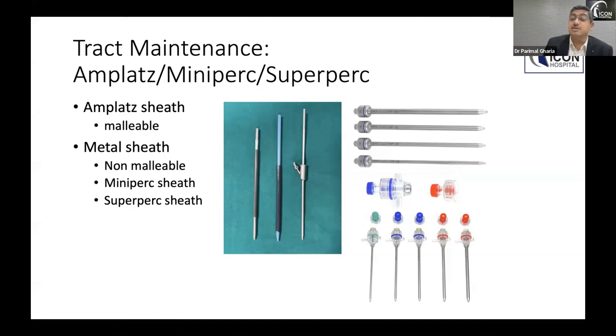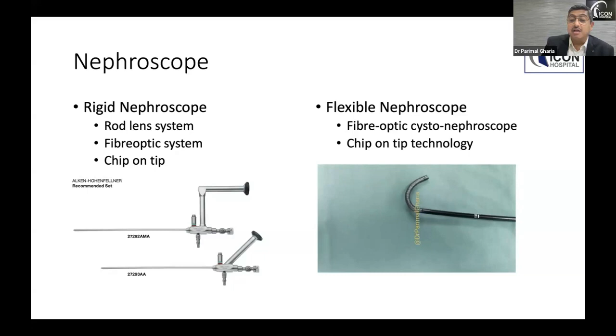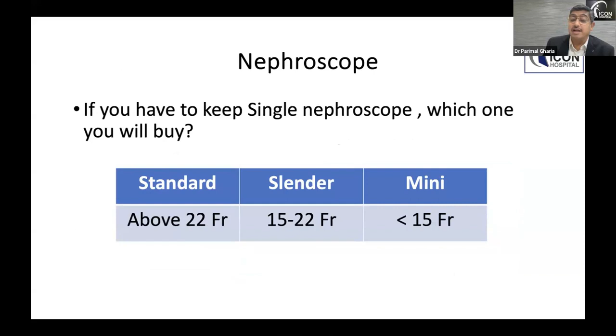Now we come to the nephroscopes. There are two types of nephroscope we basically have. One is the rigid nephroscope and another is the flexible nephroscope. The rigid nephroscope can be further divided into three systems. One is a rod lens system, another is the fiber optic cables, and the latest and newer one is chip on tip technology. The flexible nephroscopes now coming are routinely chip on tip technology. Fiber optic has been given up. So we can divide the nephroscope in three parts: standard nephroscope 22 French, and slender nephroscopes or mini nephroscopes, which are less than 15 French.